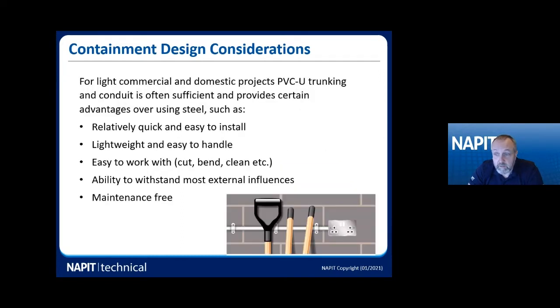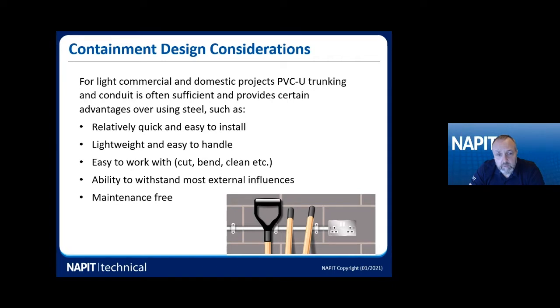For light commercial and domestic projects, a lot of clients like to use PVC-U trunking — it's light, easy to handle, easy to bend, quite cheap, and easy to work with. It'll withstand most external influences, and if you're somewhere with a lot of vapour or moisture, it's probably better than galvanized or steel conduit or trunking. Galvanized says it's rust-proof, but we've all seen damp environments where it hasn't fared well. Everything generally needs a little maintenance over a 30–40 year life cycle.